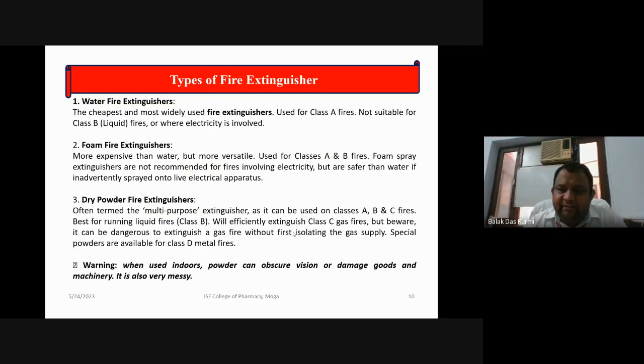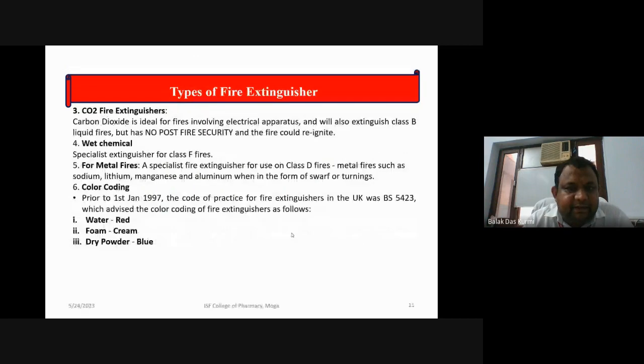So definitely this will cut out the supply of oxygen and works for running liquid fire. It will efficiently extinguish class C gas fire, but be aware it can be dangerous to extinguish a gas fire without first isolating the gas supply. Special powders are available for class D metal fires. So there is a warning with the use of dry powder extinguishers. When used indoors, powder can obscure vision or damage goods and machinery, and it is also very messy.